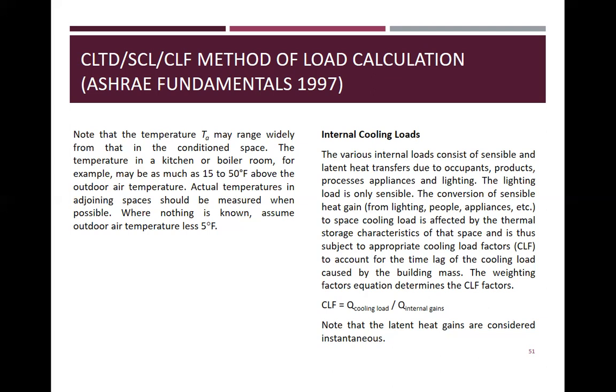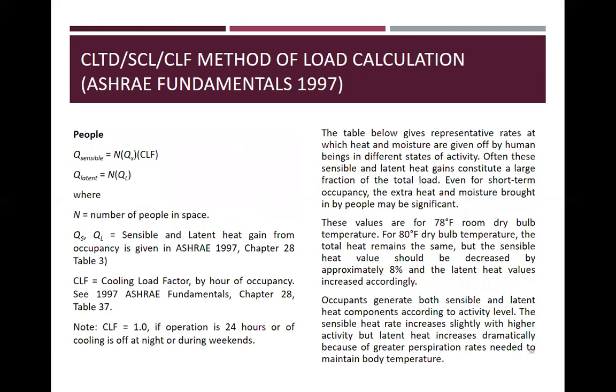The weighting factors equation determines the cooling load factors. CLF is equal to Q cooling load divided by the Q internal gains. Note that the latent heat gains are considered instantaneous. People. So Q sensible is equal to N times QS times CLF. Q latent is equal to N times QL, where N is the number of people in space, QS and QL are the sensible and latent heat gain from occupancy given by ASHRAE 1997, chapter 28, table 3. CLF is the cooling load factor, by hour of occupancy. See 1997 Fundamentals, chapter 28, table 37.